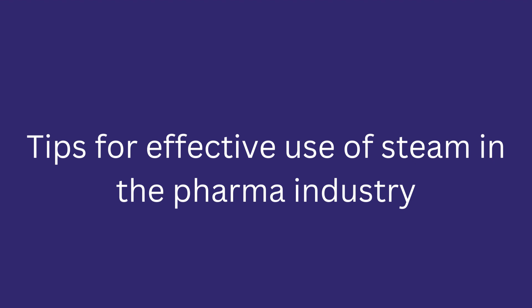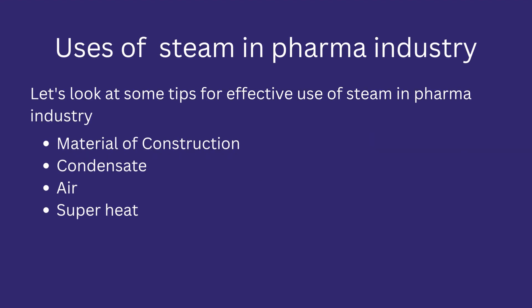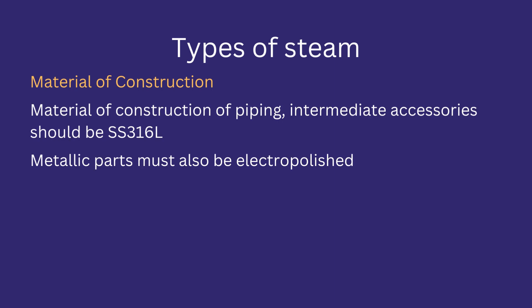Let's discuss some tips for the effective use of steam in the pharma industry. Some common areas that are helpful in determining the efficiency of steam include material of construction, condensate, air, and superheat. The material of construction of piping and intermediate accessories such as valves and fittings must be SS316L, as this prevents material degradation and prevents contamination in the steam flowing through it. Additionally, metallic parts must also be electropolished.